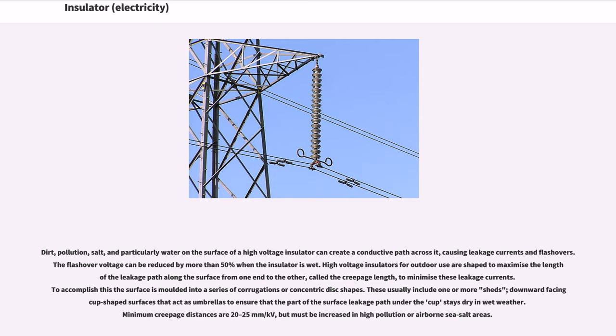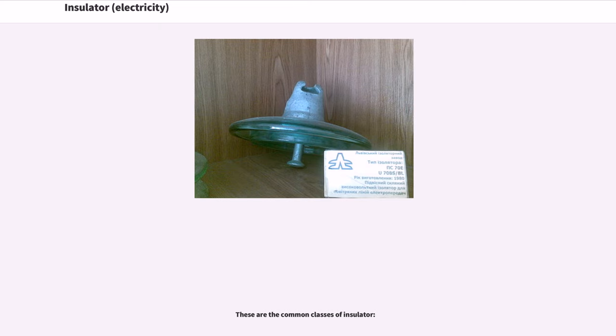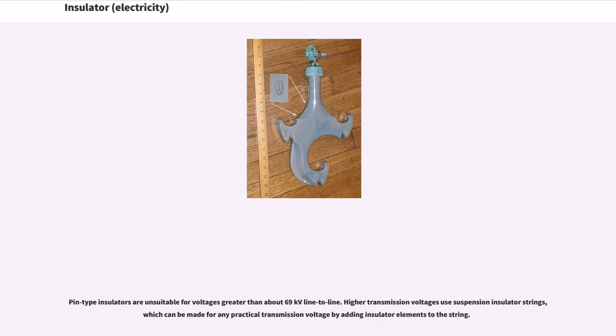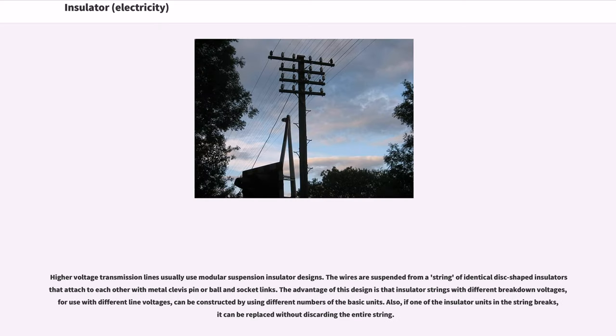Minimum creepage distances are 20 to 25 millimeters per kV, but must be increased in high pollution or airborne sea salt areas. Pin-type insulators are unsuitable for voltages greater than about 69 kV line to line. Higher transmission voltages use suspension insulator strings, which can be made for any practical transmission voltage by adding insulator elements to the string. The advantage of this design is that insulator strings with different breakdown voltages can be constructed by using different numbers of the basic units. Also, if one of the insulator units in the string breaks, it can be replaced without discarding the entire string.